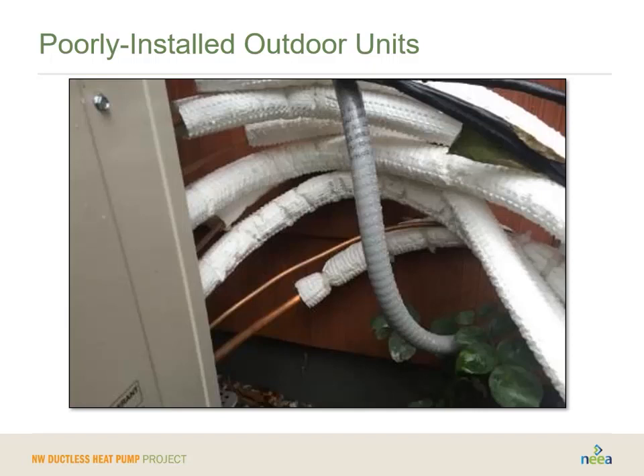I kind of hinted at this earlier, but one of the tricks is to push back the insulation when you're making the connections and then let it kind of accordion back out to cover the entire line set. In this case, it was simply trimmed back too far to make it easier for the connections, but now we're going to have a poor performance over the long term.